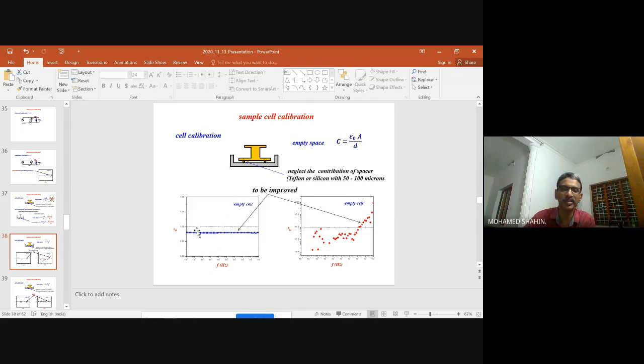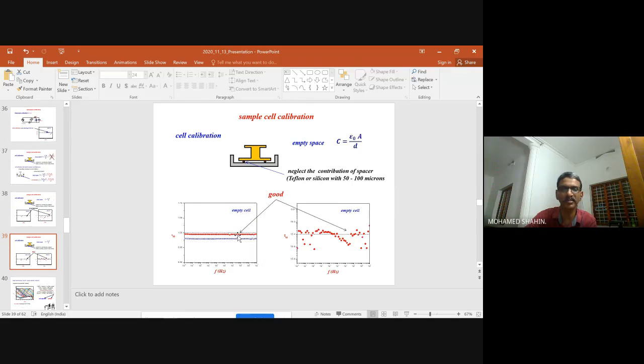Then after doing that, before doing the cell calibration, you will get different epsilon prime. Now after the cell is properly calibrated, the permittivity would be exactly coming towards 1. Otherwise it had been slightly lesser than 1. Then the loss is something like what is the background? You have to remove all the backgrounds. For removing the background, you ensure that there is nothing in between.